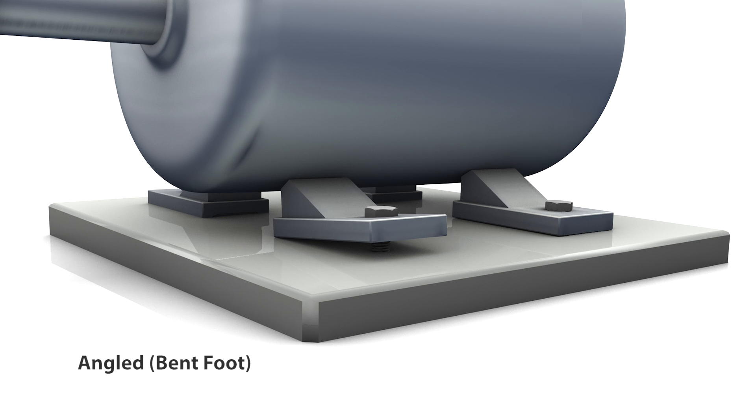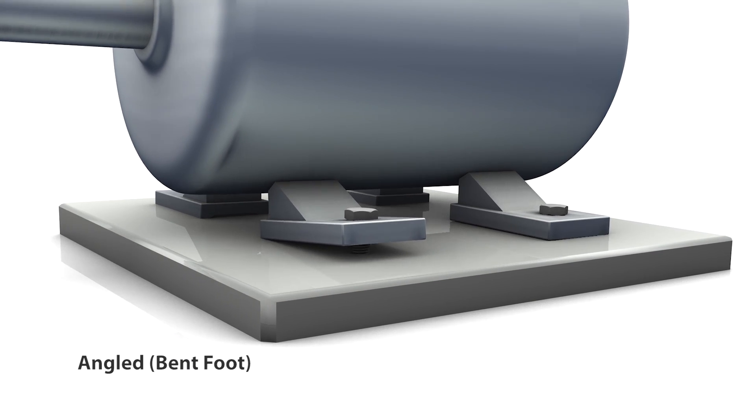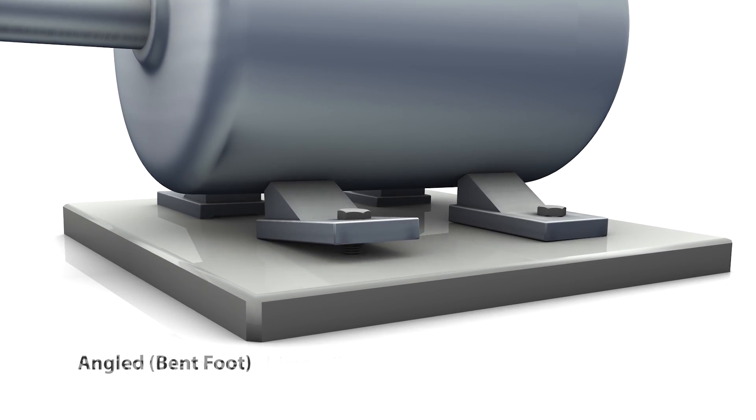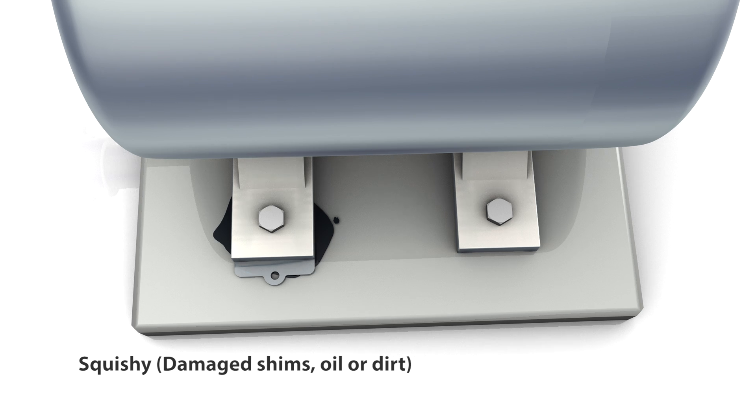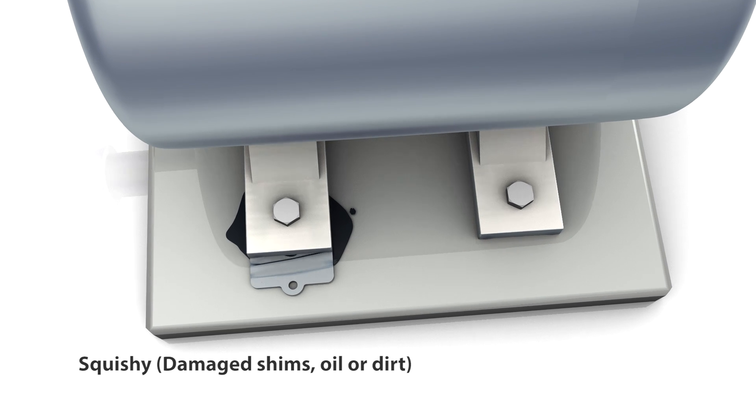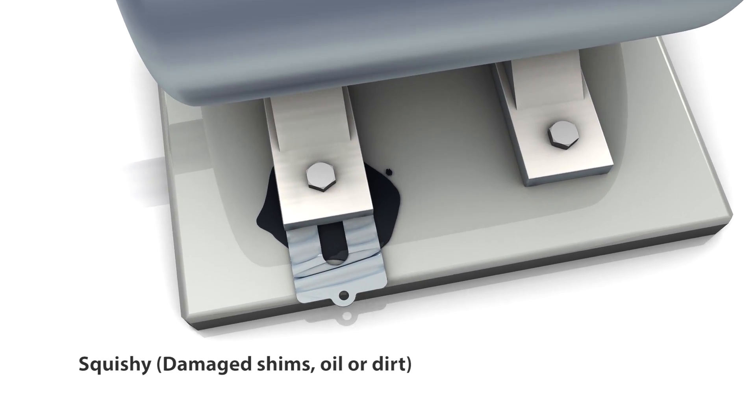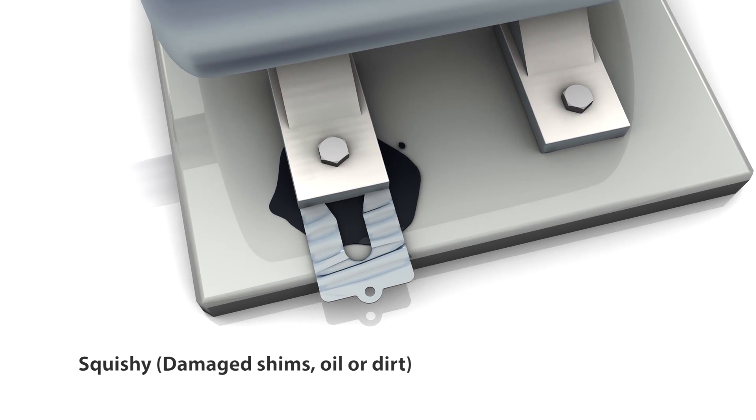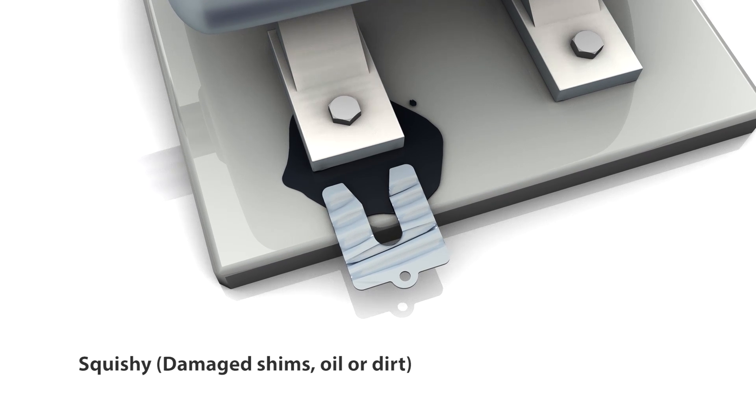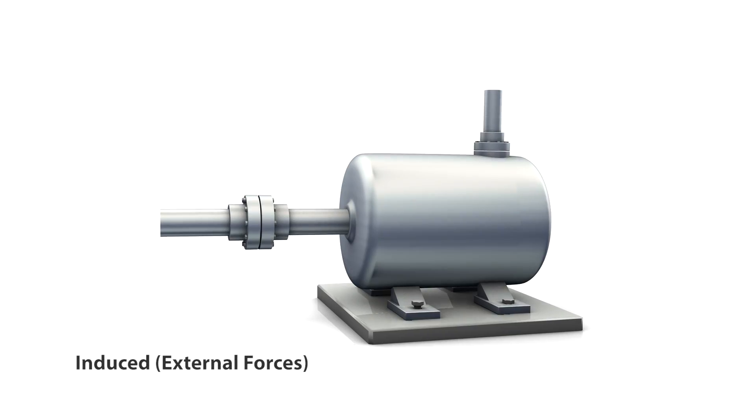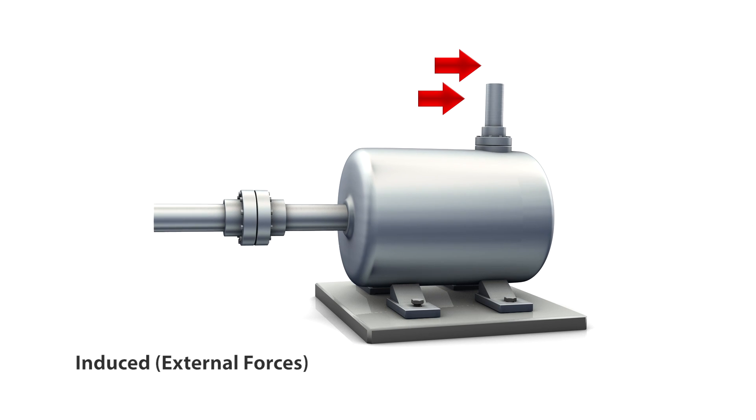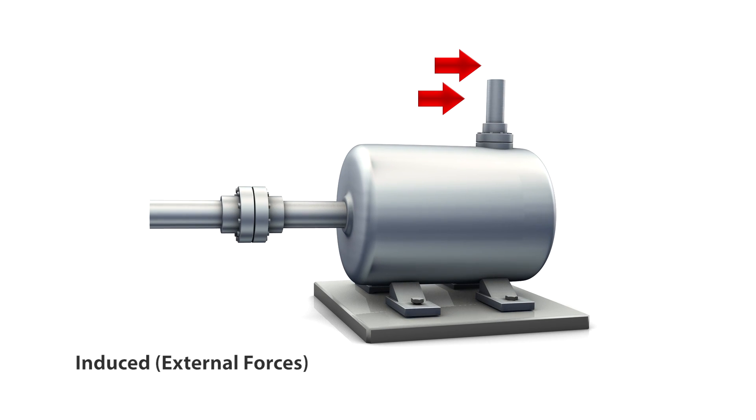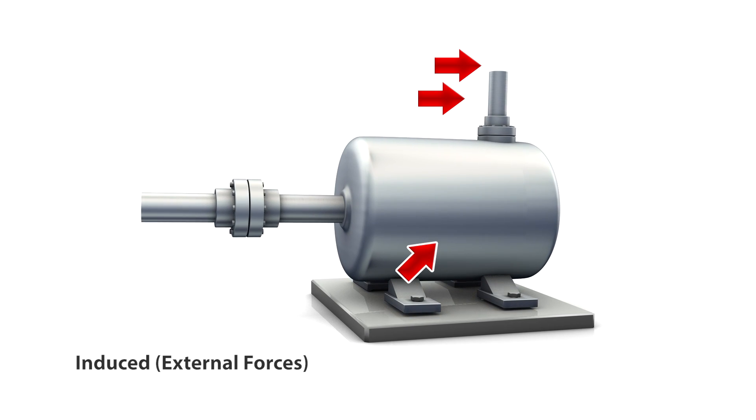Squishy soft foot occurs when worn out shims or contamination by dirt or oil impair proper seating of a machine. Induced soft foot occurs when an external force such as pressure from attached piping or other equipment causes displacement of machine feet.